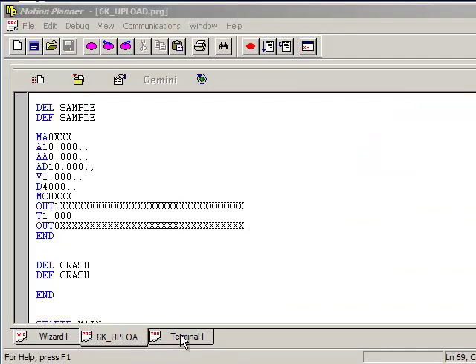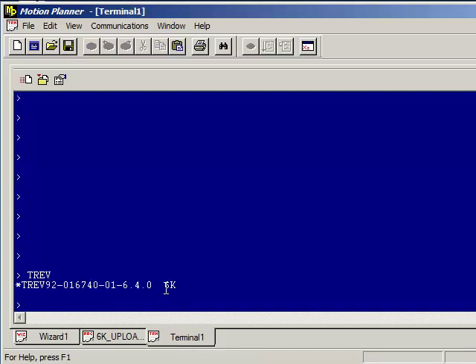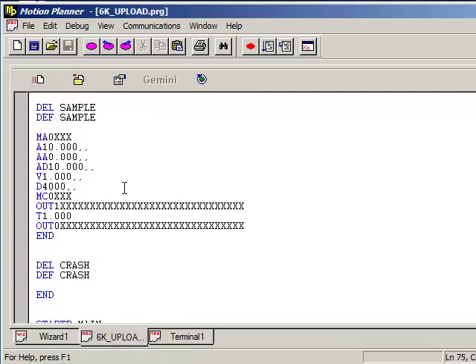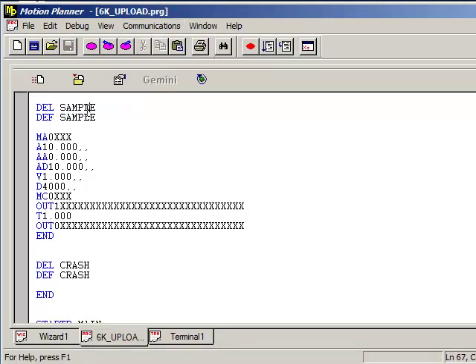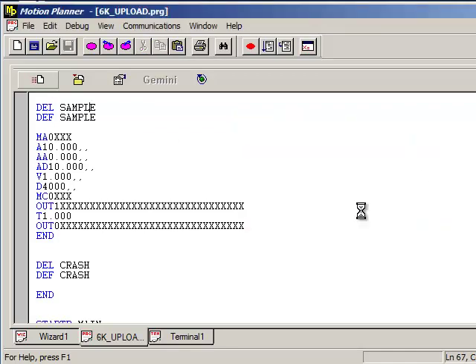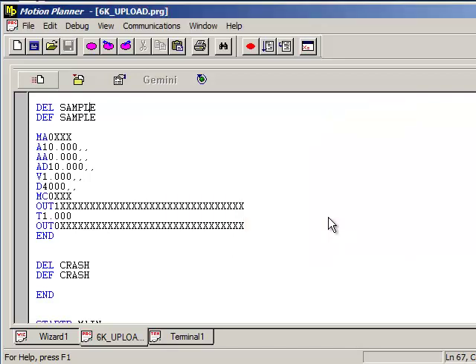So now you've saved the program. If you then power down and then connect your new 6K controller, go in the terminal window, you want to verify you're talking first before you start doing any downloads. You can type TREV, verify that you're getting a response. On the program editor screen, go back. You can go into communications download editor, or on the left hand side, you'll see the icon for download editor. It'll go ahead and, with the default, send a kill to any tasks that are running. So go ahead and press OK.